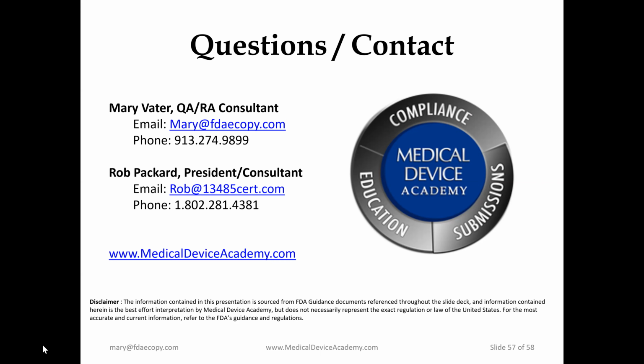If I were going to do it, number one, I would be filling out my letter to file decision. Is this something that requires a 510K or not? Go through the decision tree. And number two, I would be seriously considering doing a pre-sub with the FDA to see if the FDA feels that it's something that needs a 510K.